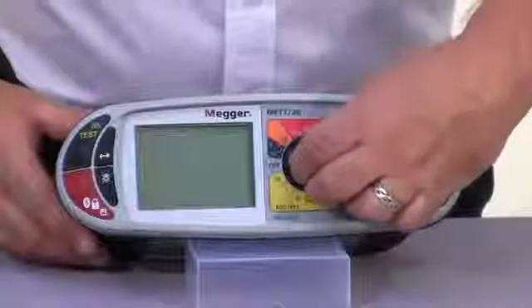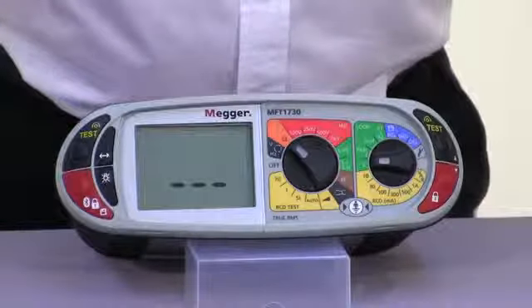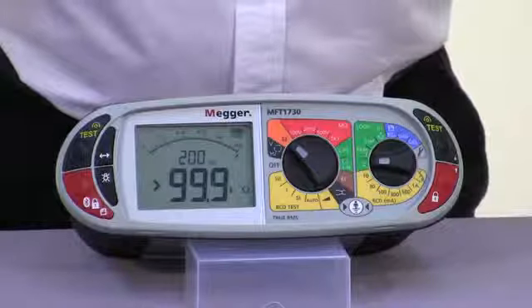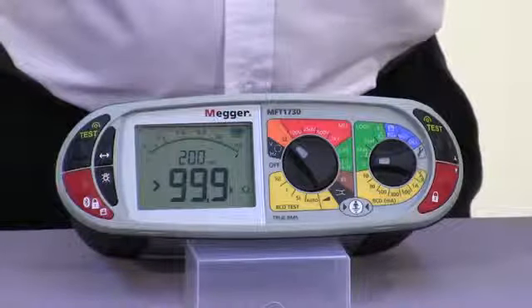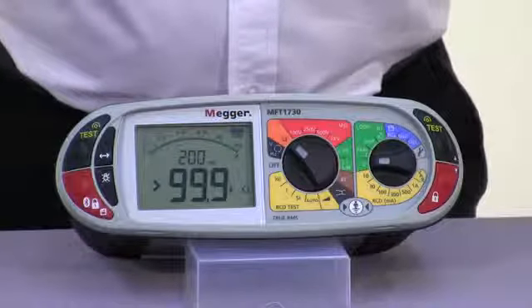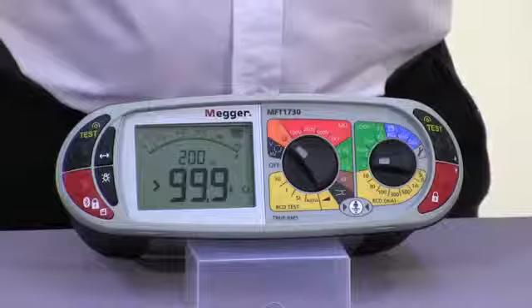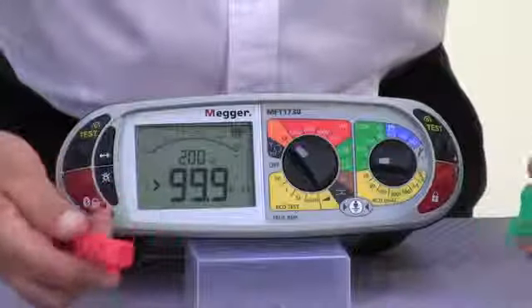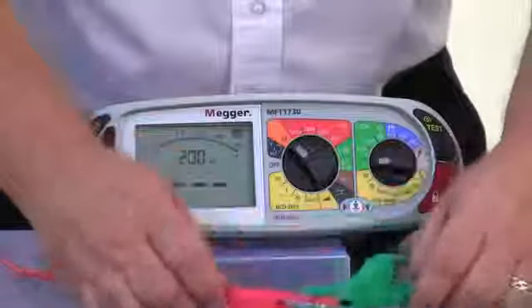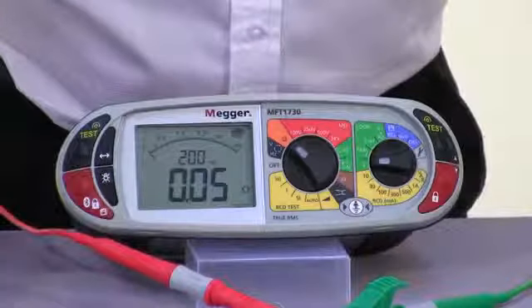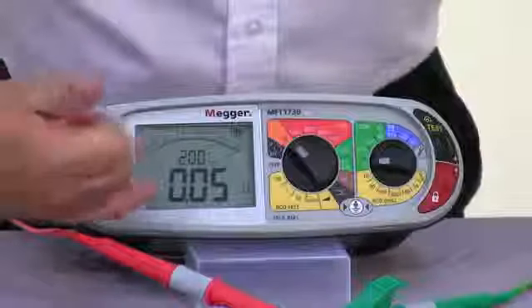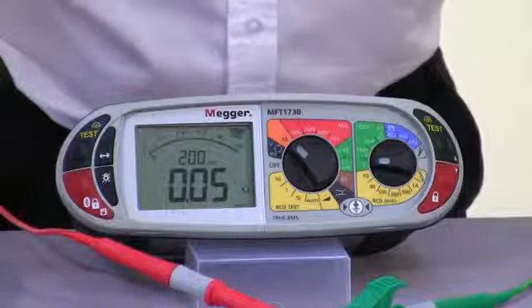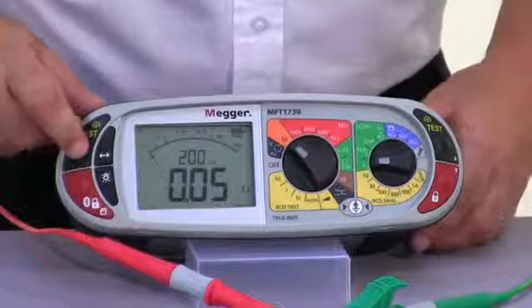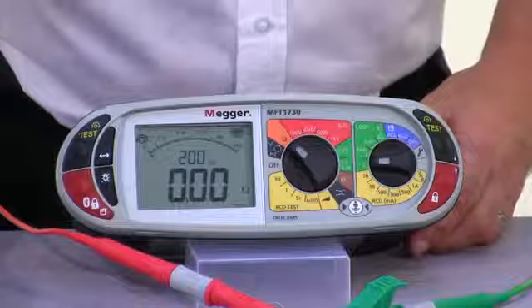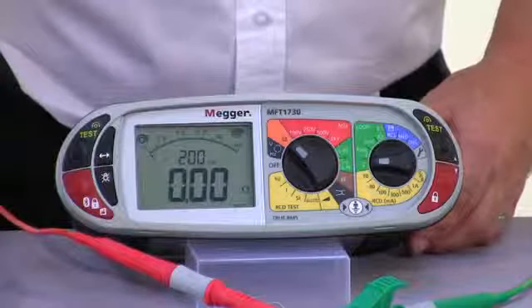Okay, selecting continuity measurement, the first thing that we'd need to do is look to null out the resistance of the lead set. One of the features with the MFT1700 series and the Megger range of insulation continuity testers is the auto start. So as you see, when I connect our leads together, the unit will start the test automatically. Now you'd heard there that we've got an audible indication, and it's confirming that we've got a stable reading. So now pressing the test button, this will actually take in the compensation of the lead null, and we get an indication on the screen to confirm that the null is in place.